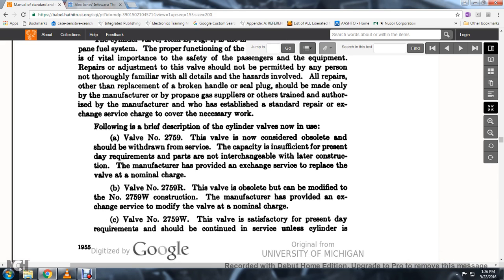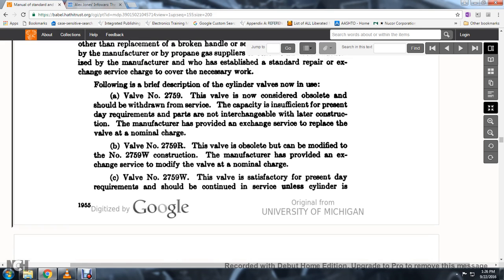The valve No. 2759: this valve is now considered obsolete and should be withdrawn from service; its capacity is insufficient for present-day requirements, and parts are not interchangeable with later construction. The manufacturer has provided an exchange service to replace the valve at a nominal charge. Valve No. 2759R: this valve is obsolete and can be modified to No. 2759W construction; the manufacturer has provided exchange service to modify the valve at a nominal charge.